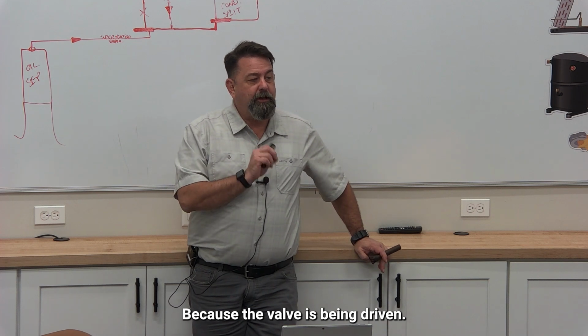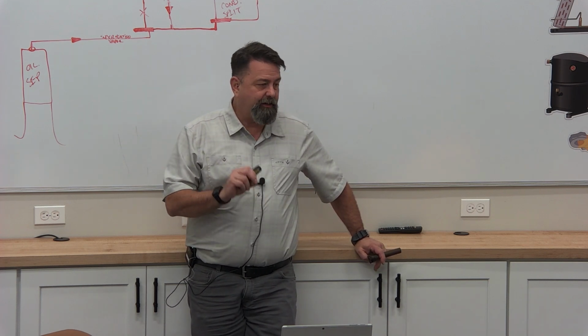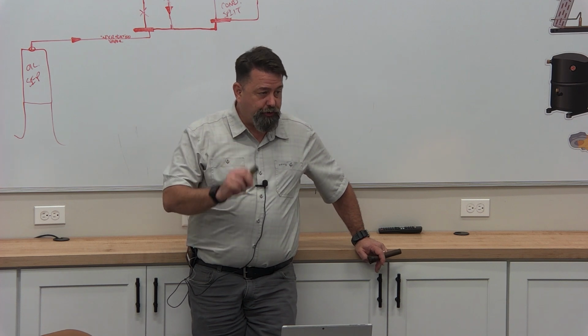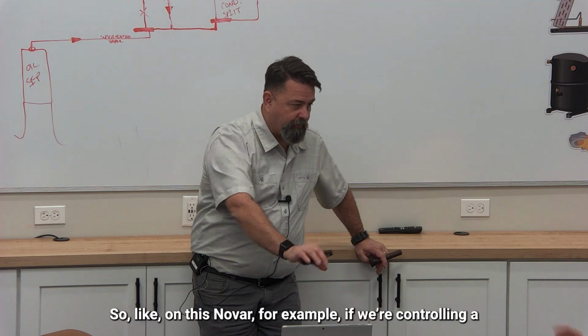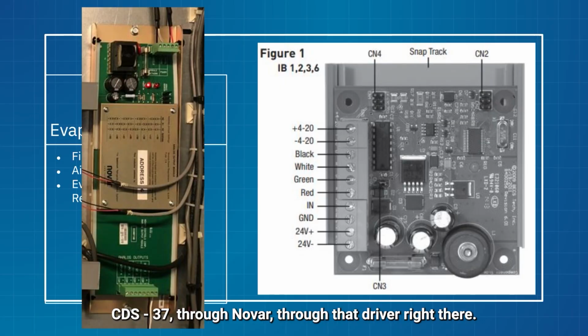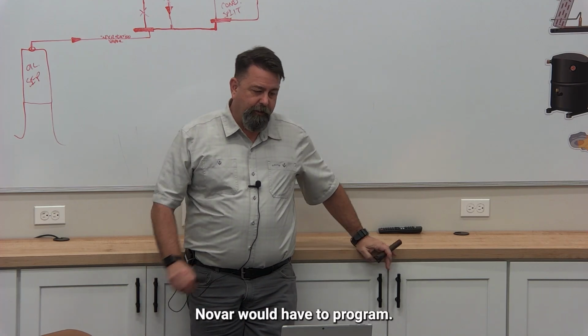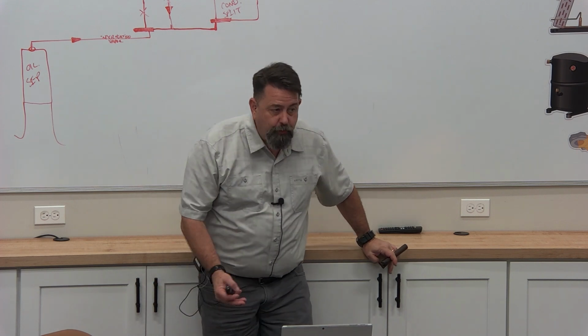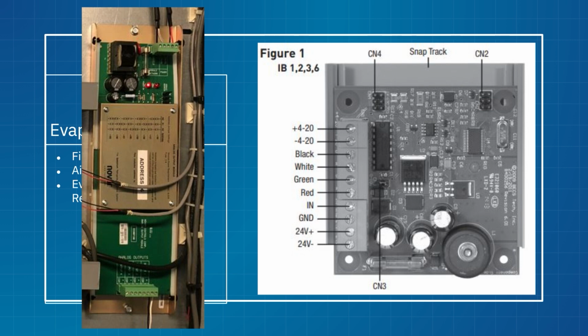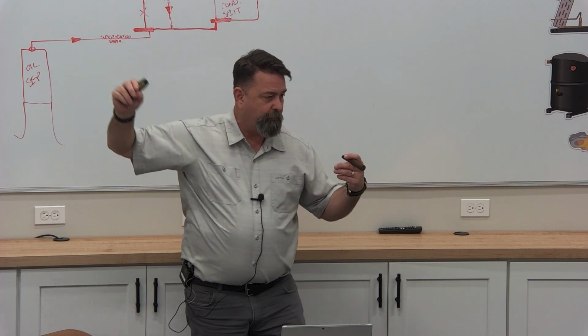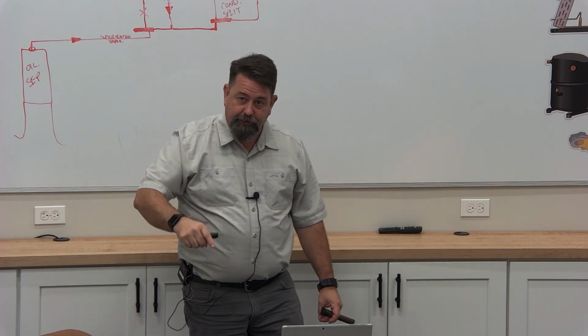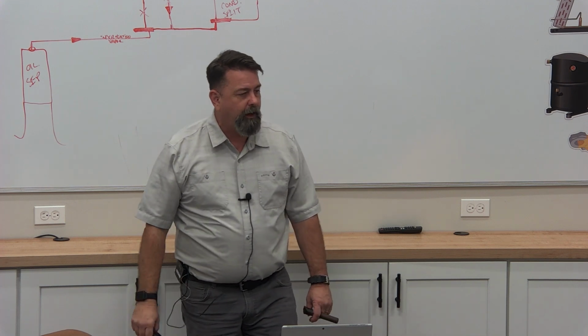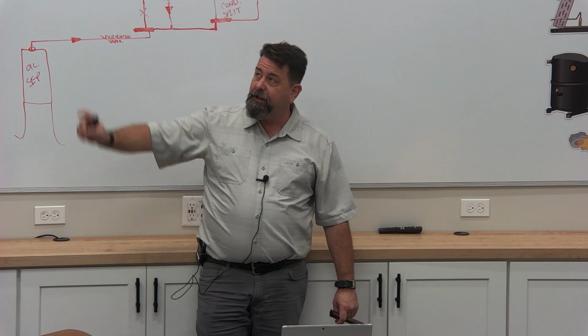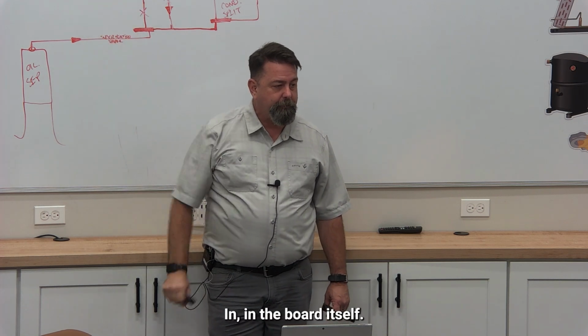No, good point. The EMS valve system is being driven - my EMS system is not telling it to overdrive, unless it's controlling a module itself that drives it. So on this Novar, if we're controlling a CDS-T7 through that driver, it's just going to say Novar 0. They're not going to say go to minus 2 volts, it's just going to say 0. This board is then going to interpret that 0 and drive it over 10% beyond its last count - it's going to count down to 0 and try to drive it 10% more times, so it knows it's at 0. That's going to be in the valve driver itself that's doing that, in the board itself.